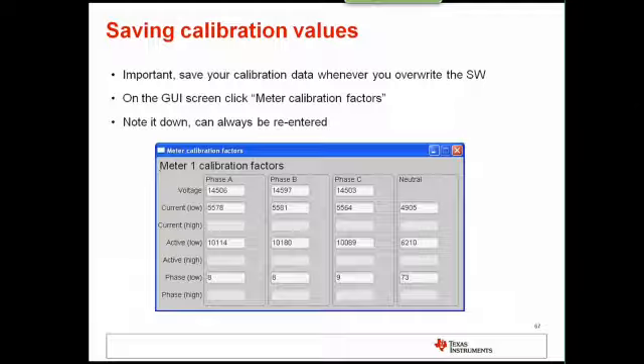We're starting to run a little close to the end here. Once you have all this data inside your GUI, you can open up the meter calibration factors I showed you before, copy this out, and record it for that meter. If you're going to take it to a customer and let them help calibrate it, make sure they save this off so they can return to these points later in the day. You can also use these as a kind of golden reference value — input them into the source code, program it into another meter in production, and you can get pretty close to your calibration points.